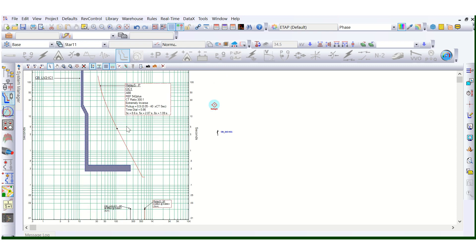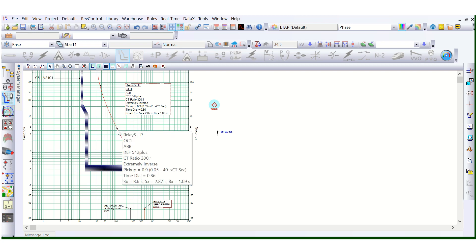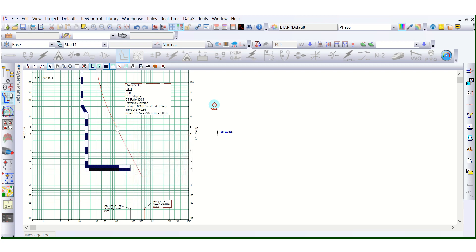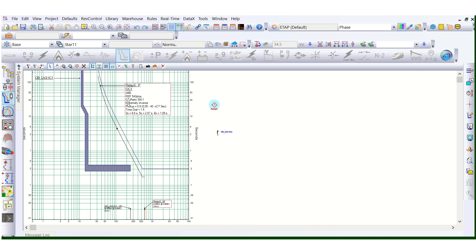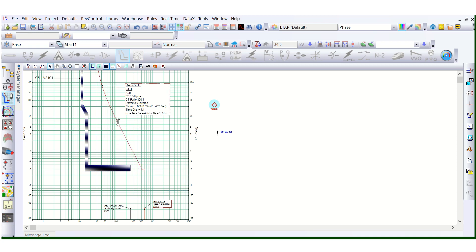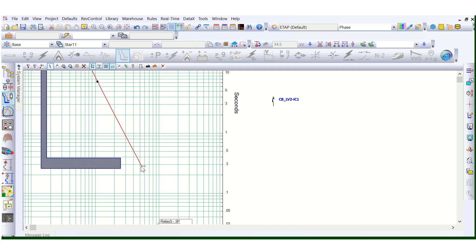This is the inverse characteristic, and how long it will maintain its inverse characteristic — as you can see when I drag this curve, this is the minimum time dial at 0.05 and the maximum time dial is 1.5. This is the range where it can operate. Up to this point, we can use the cursor to read the value.